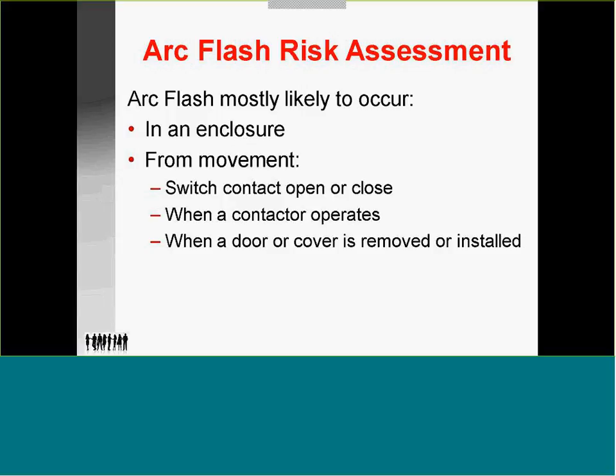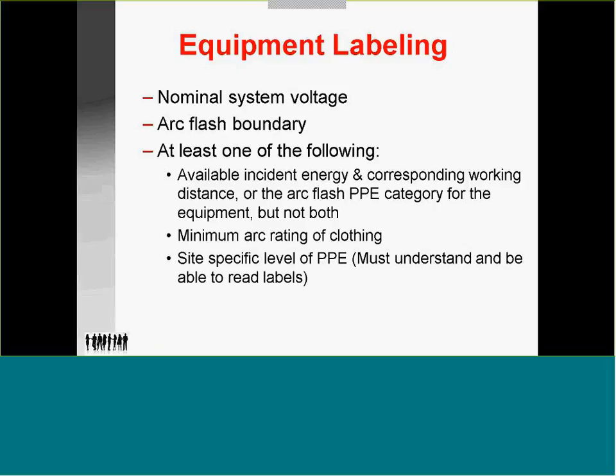Then when a door or cover is removed or installed, that is where a fault can begin. And microscopic debris at the time, and you open a door or slam it shut, it can initiate the arc to begin. Once the arc begins, the fault current begins feeding. As time passes, this will keep increasing. For a time it can be held within the panel or cabinet, then break out depending on the current coming in and the clearing time from the source.